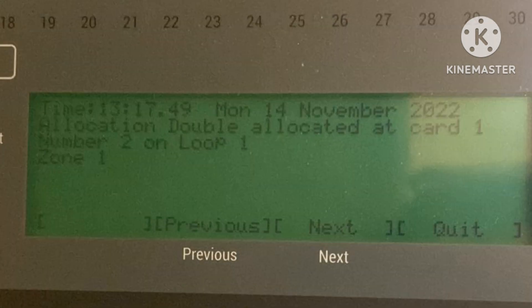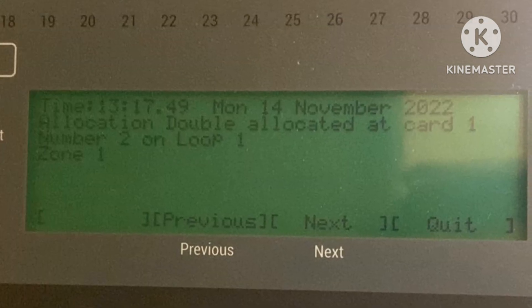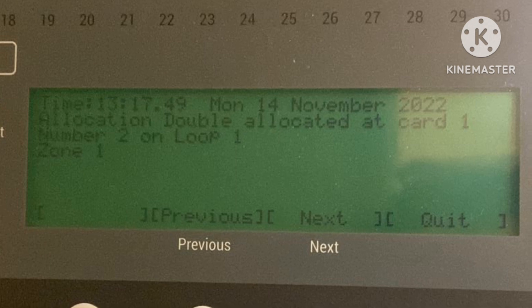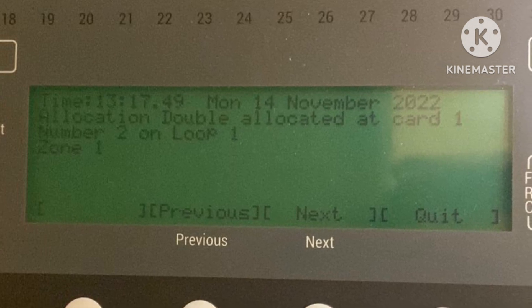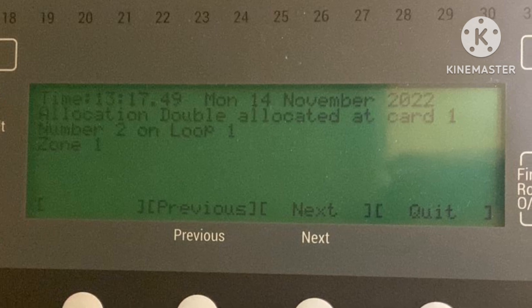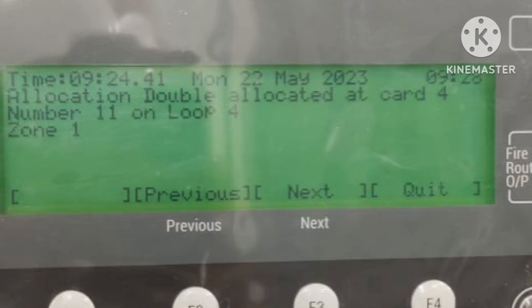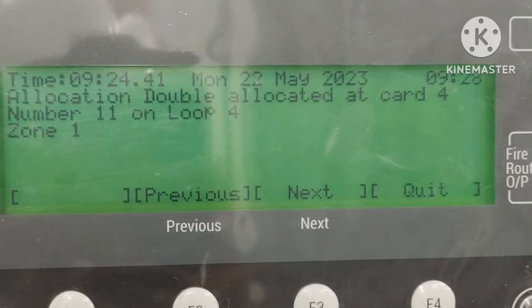In this case, we have to check the connections and the device. Go to the device, open it, and check its condition and status. Remove it, check, and put it back again. For example, 'Allocation double allocated at card 4, number 11, on loop 4' — go to loop 4, device number 11, check if the device is faulty or has a bad connection. After checking, reallocate and the fault should clear.